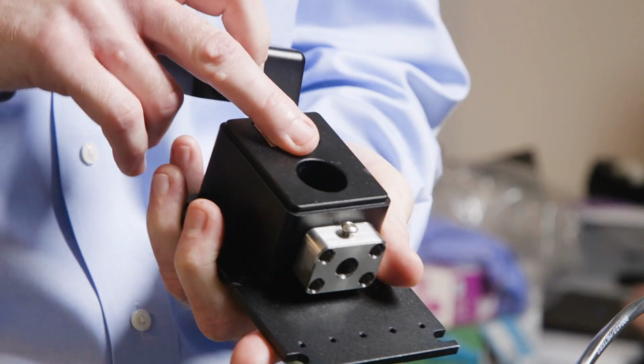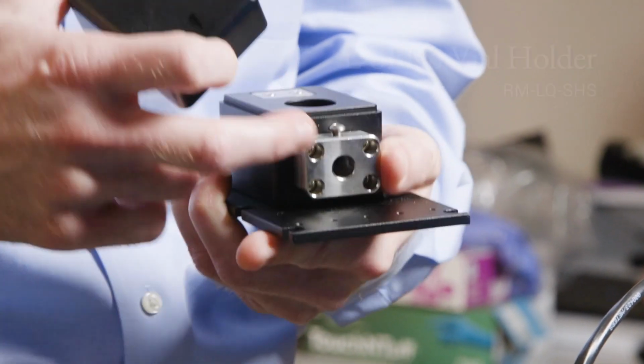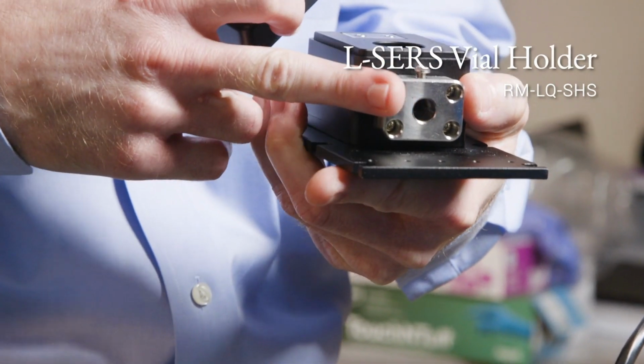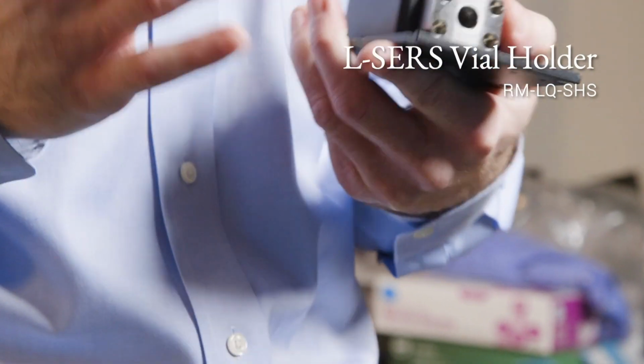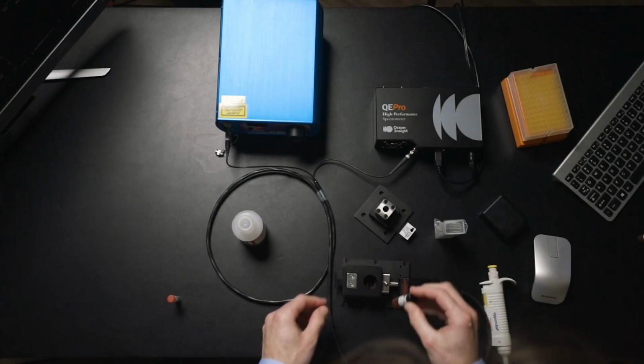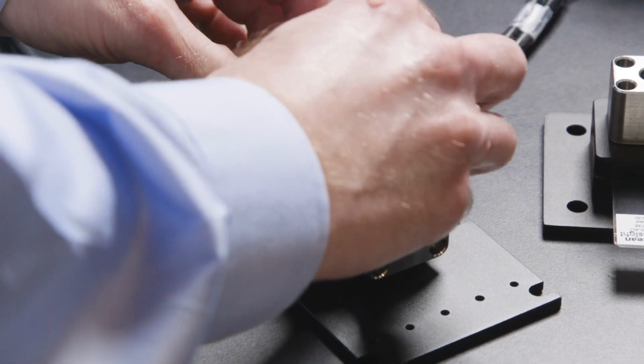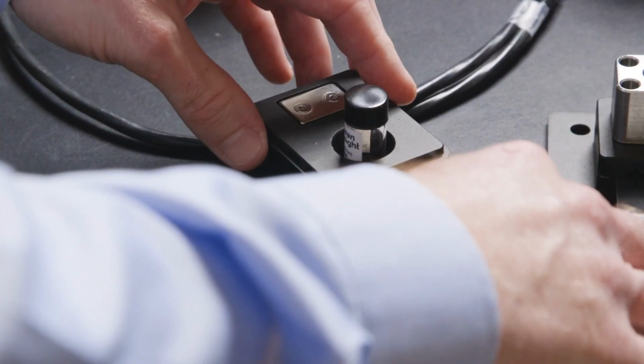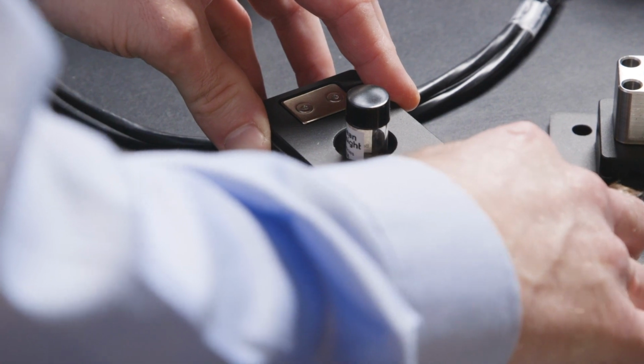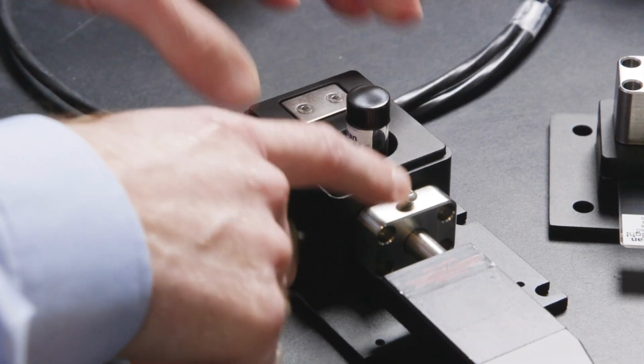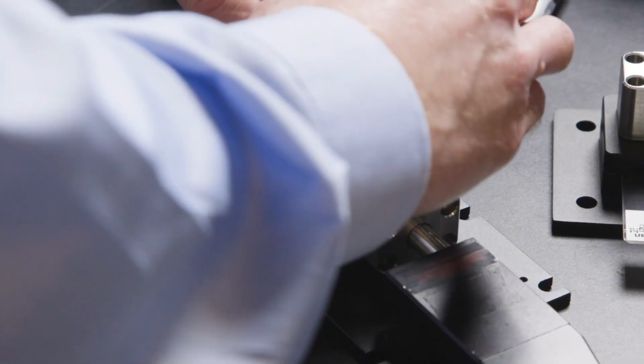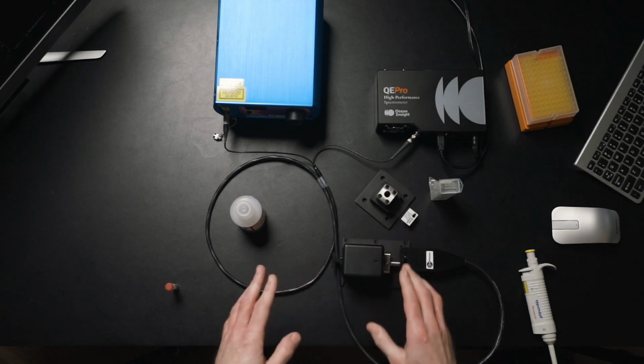So we have another great accessory here, a vial holder that lets you put this right into the sample holder and then have the probe butt up right against the vial, and it's focused perfectly so that you're having that Raman laser focus right in the middle of that analyte solution. So we're gonna go ahead and place the LSERS into the holder and put the laser right into its respective holder. And there's a set screw here to make sure everything is nice and secure. Put the cap on. Then let's take a background scan.